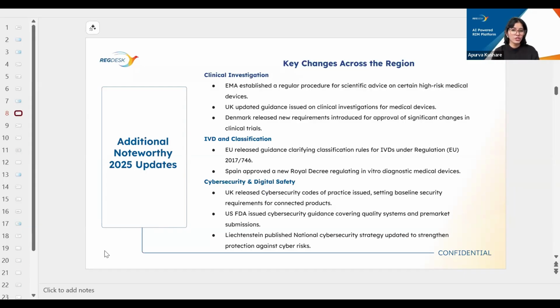The US FDA also issued a cybersecurity guidance covering quality system and pre-market submissions. This document provides FDA's recommendations to industry regarding cybersecurity device design, labeling, and also the documentation that FDA recommends be included in the pre-market submissions for devices with cybersecurity risks. We also have another cybersecurity document released by Liechtenstein. They have published an updated national cybersecurity strategy to strengthen protection against cyber risks. As you can see, there's a lot of action happening around cybersecurity. It is becoming a top priority and a main hot topic in the regulatory world currently.